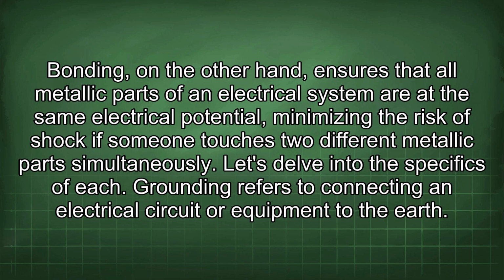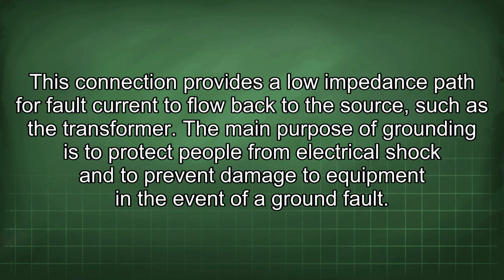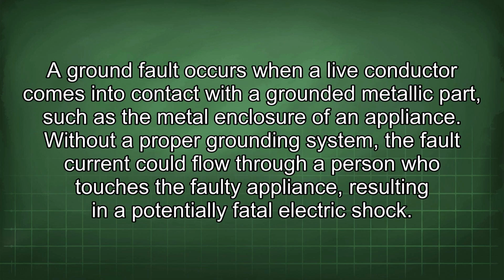Grounding refers to connecting an electrical circuit or equipment to the earth. This connection provides a lower impedance path for fault current to flow back to the source, such as the transformer. The main purpose of grounding is to protect people from electrical shock and to prevent damage to equipment in the event of a ground fault. A ground fault occurs when a live conductor comes into contact with a grounded metallic part, such as the metal enclosure of an appliance. Without a proper grounding system, the fault current could flow through a person who touches the faulty appliance, resulting in a potentially fatal electric shock.